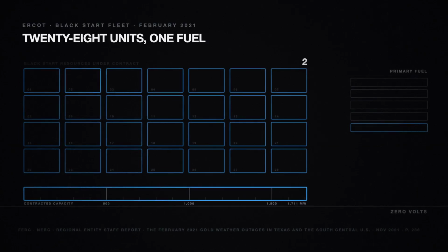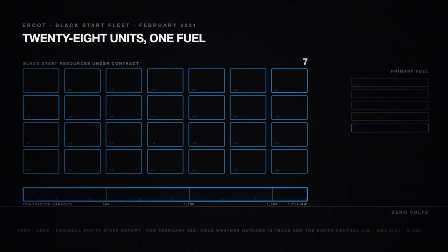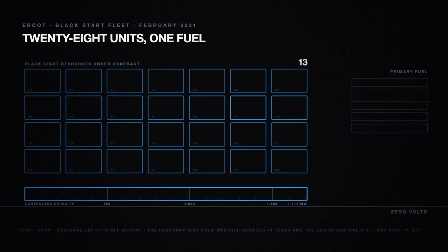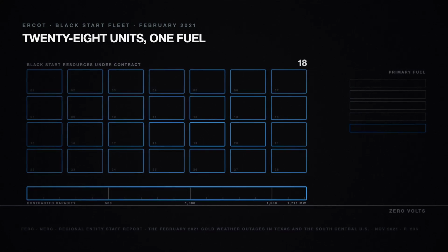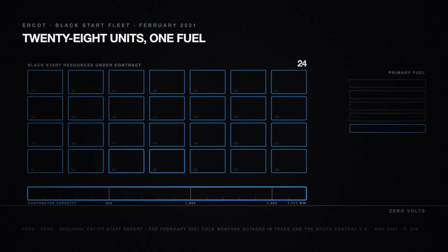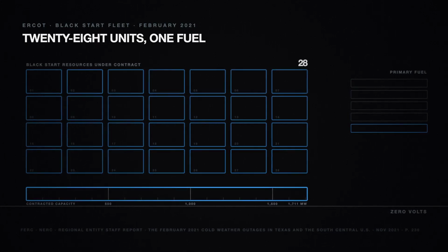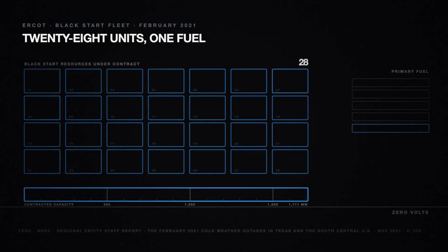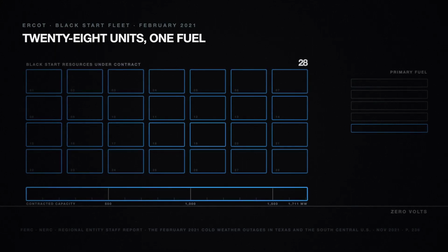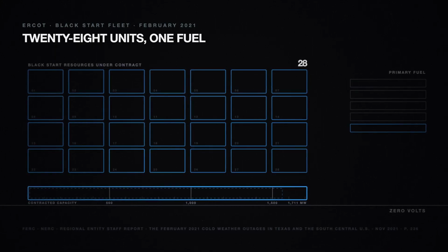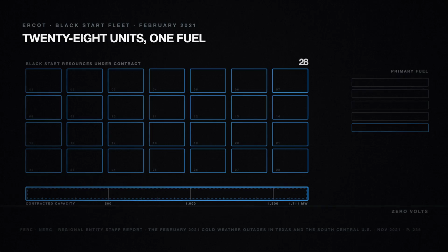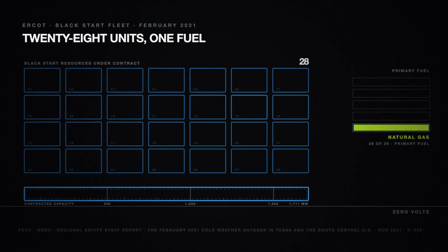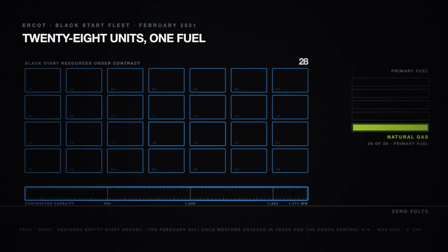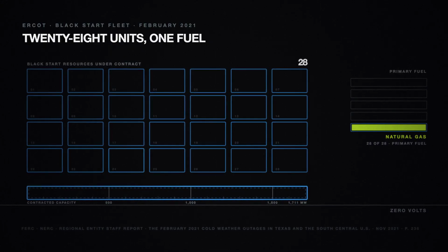That 4-minute figure comes from the grid operator's own slide deck to Congress. Across 23 slides, that deck never uses the phrase black start once. This is what it did not discuss. 28 machines. That is the black start fleet the Texas grid operator had under contract in February 2021, 1,711 megawatts between them. All 28 used natural gas as their primary fuel. Not most, all, no diversity at all.